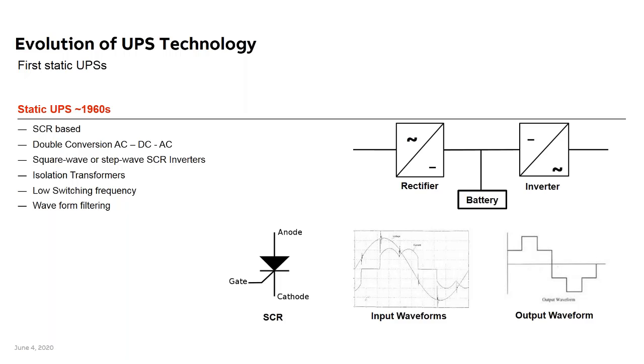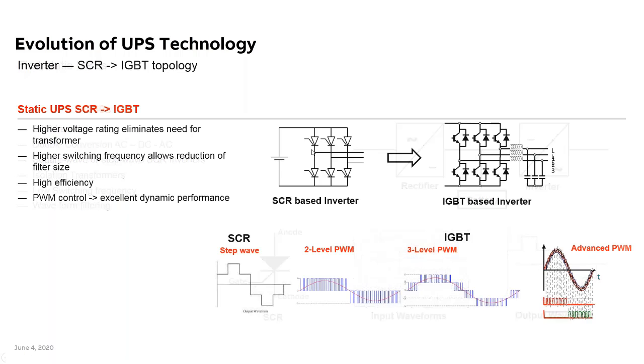First of all, the rectifier would generate a lot of harmonics that would be fed back up the power lines. And the inverter would, in some cases, just be a 60 hertz square wave. In the best case, like this, it could be a step wave, but would require significant filtering to look like a sine wave, which was required for the critical load. So that's where we started out with static UPSs.